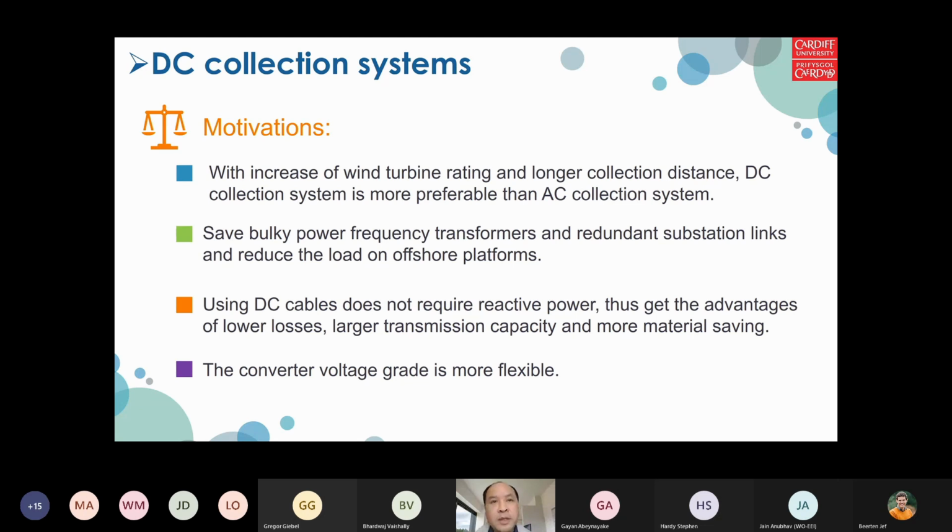But in the past, we know that the break-even distance generally for the overhead line is hundreds, 800, 600, thousands of kilometers. For the offshore, 50, 100 kilometers. That's the break-even. So according to that rule of thumb, okay, we think the connection system is only several kilometers or 10 kilometers within that wind farm. So, without further comparison, we know that might not be feasible. Okay.